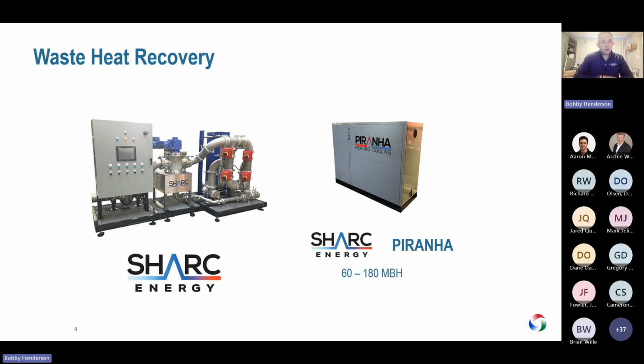Switching gears a little bit out of the boiler room, SHARC Energy, you may have been familiar with. We've done coffee breaks in the past. SHARC specializes in wastewater heat recovery. So you're looking at a couple products here. On the left would be the SHARC system, which is a wastewater energy recovery system typically for district heating and cooling. So we're basically capturing wastewater energy, or we are sinking to wastewater to produce typically condenser water for large central energy plants, such as at the National Western Center, if you're familiar with that project.